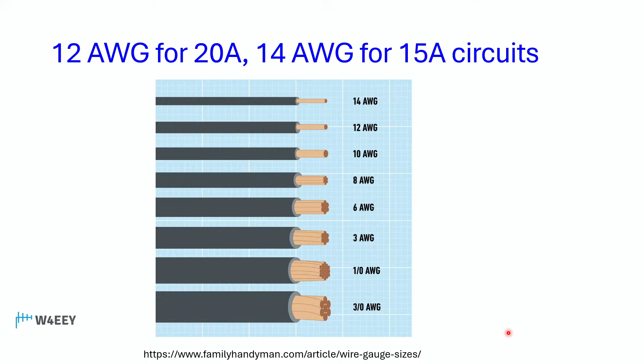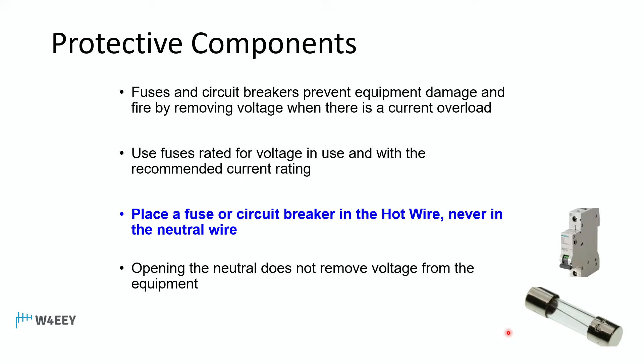Protective components. Fuses and circuit breakers, we've talked about circuit breakers. Fuses also in equipment. You want to use them so that they're rated for the voltage in use and with the recommended current rating. And the current rating, if it's a 250 volt fuse, you can use it in a 120 volt circuit. That's fine. That's just its maximum voltage. And then the current rating will stay the same no matter what the voltage is.